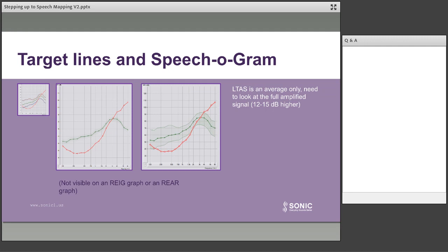And so when we look at this now, we can see that there is a lot of audible sound in those high frequencies, but only for the louder parts of that. And you wouldn't see that. These are exactly the same targets, the same algorithm as what you would see in insertion gain, but because insertion gain doesn't show you threshold, you never get a real feel of what's going on. And so the minute that we start looking at what the speechogram is, and we're looking at threshold as well, we now begin to have a greater understanding of the output of the hearing aid and what we're doing.